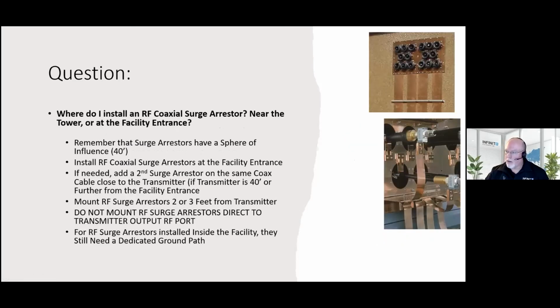So for RF coaxial surge protection, where do I install that surge arrestor? A lot of folks, not in the broadcast world, but other people sometimes say, I want to put it right at the antenna on my tower. And I say, well, that's a waste of space. Remember that 40 feet of influence? It's not doing any good on a 100-foot tower. So put it at the cable entrance where the cable penetrates, like here. But if your transmitter or receiver or radio is 200 feet away, then you need another one on the same coax cable about 2 or 3 feet from the radio.